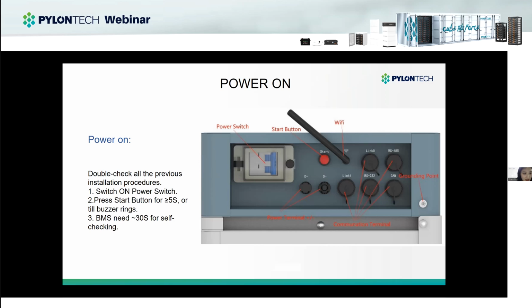Then here is the procedure of the power on. First, you should double check all the previous installation procedures. Check that the communication cable and the power cable are connected successfully. Then when you have checked that everything is okay, switch the power switch from right to left. Then press the start button for more than 5 seconds. The BMS needs 30 seconds for self-checking.